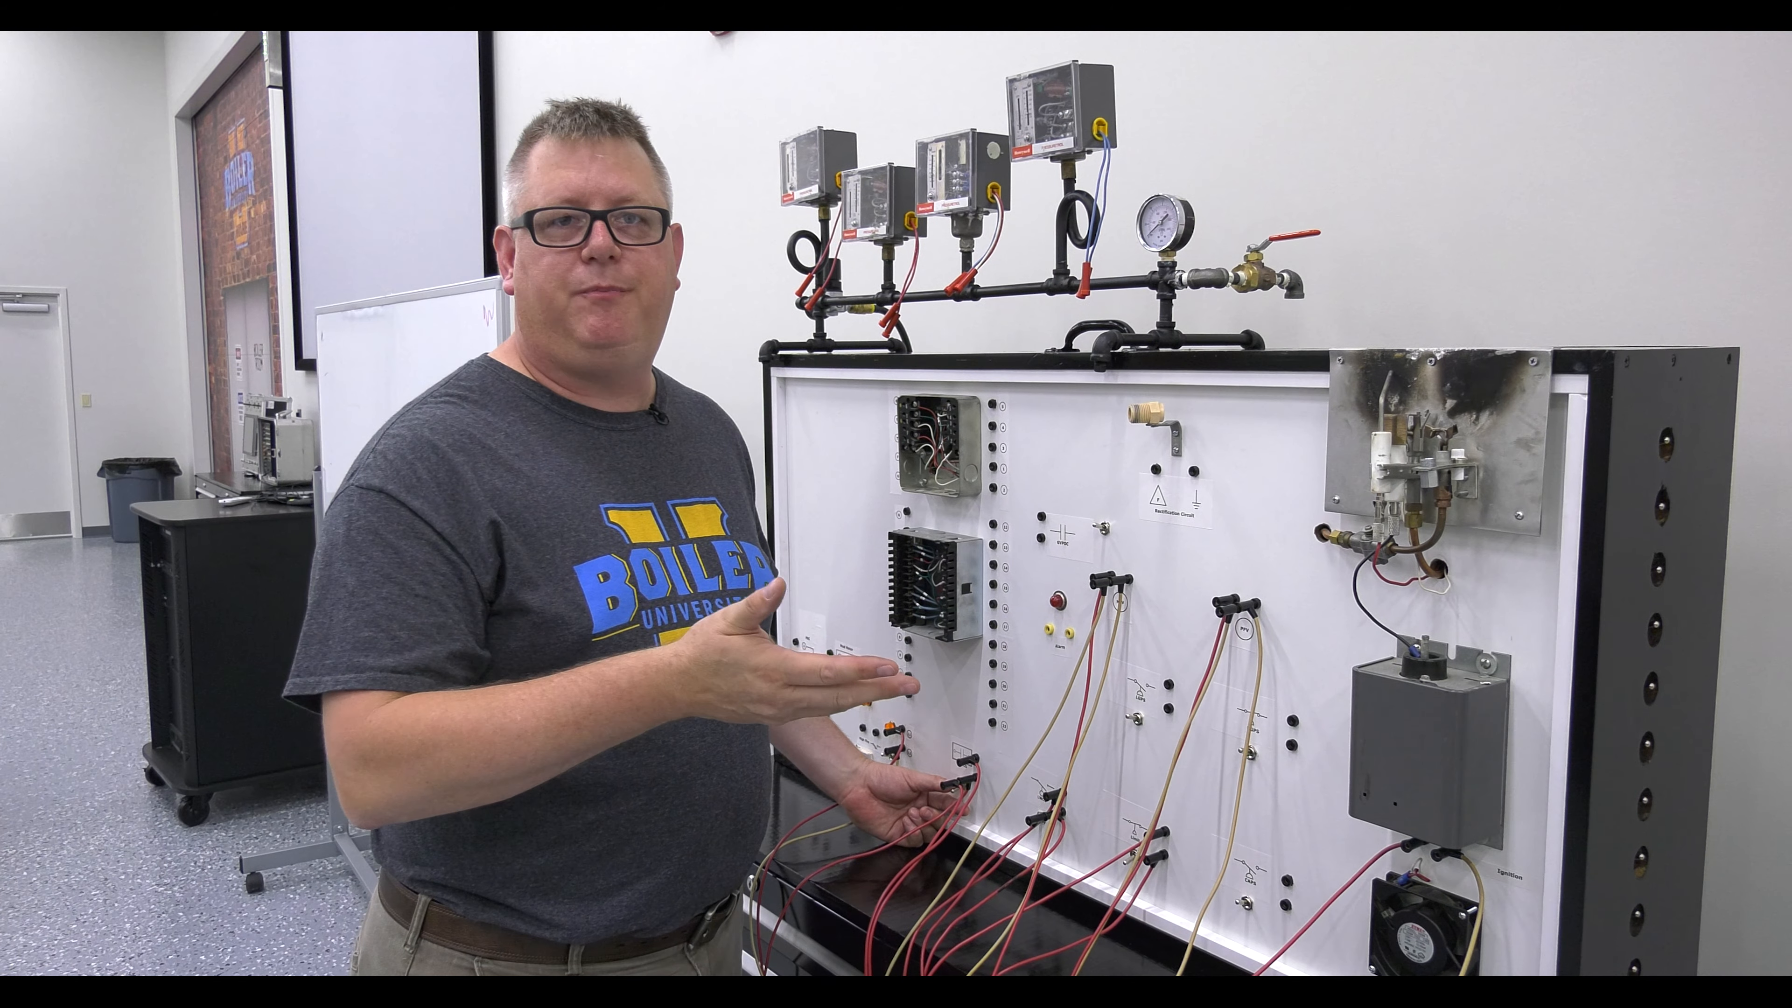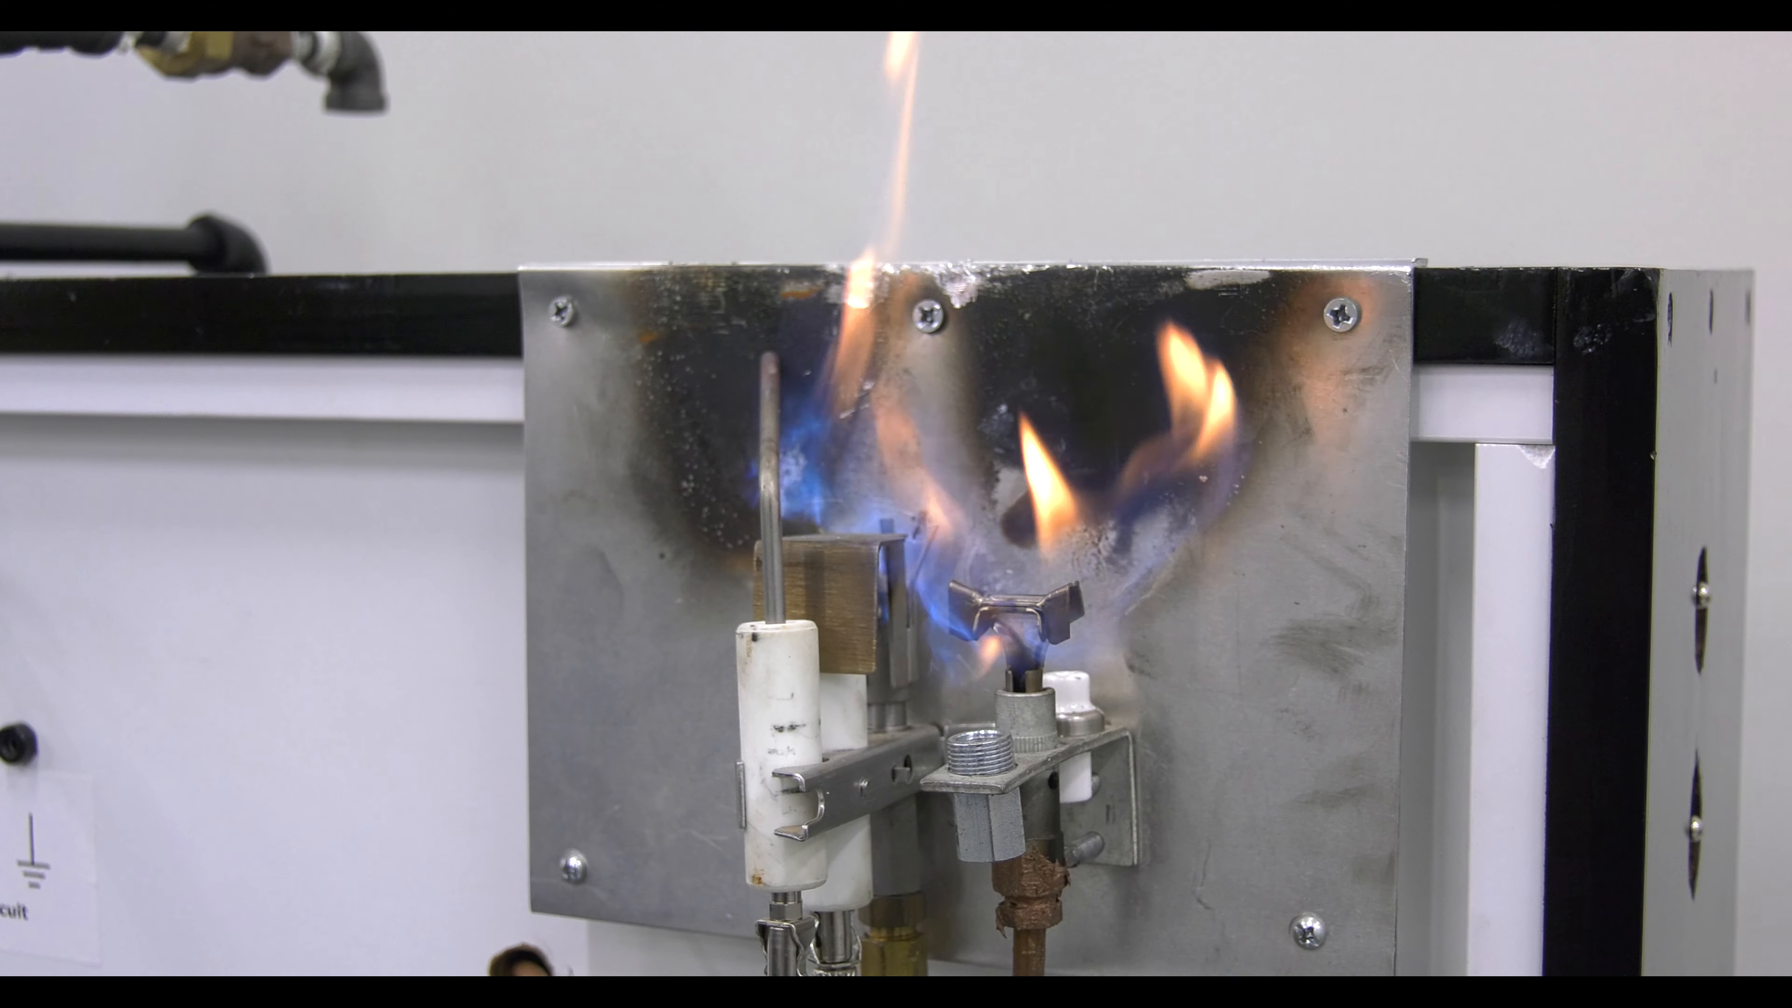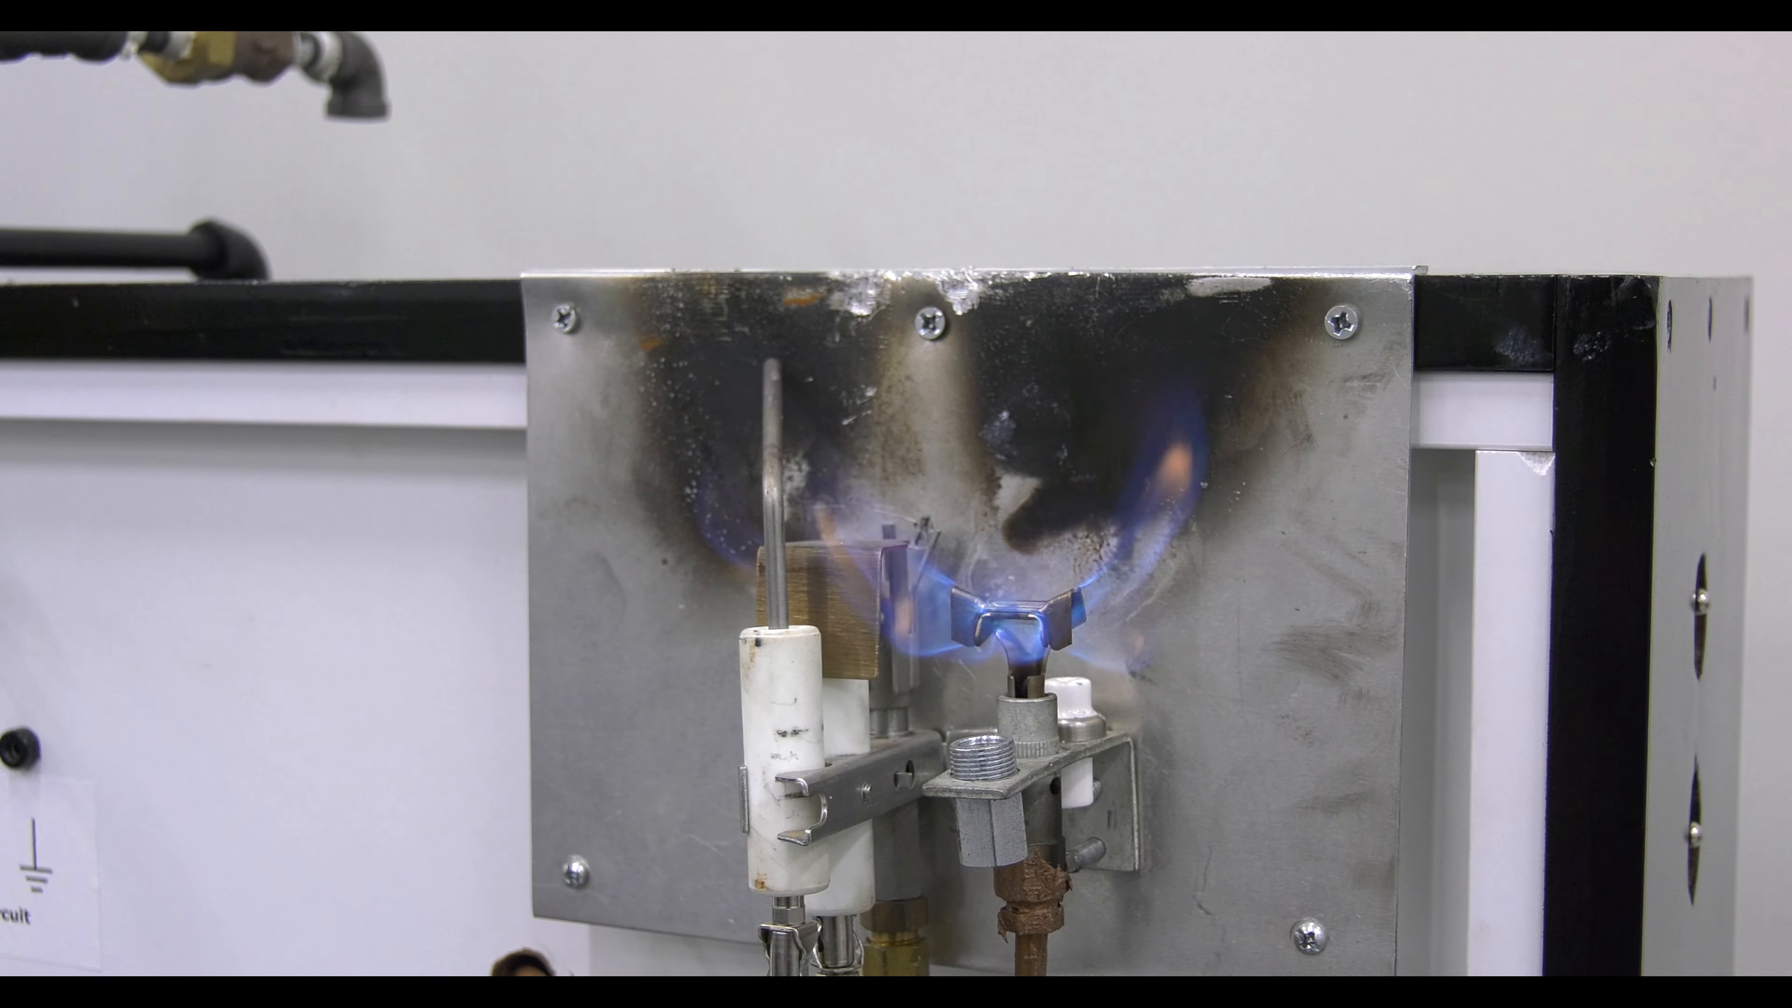The second type of pilot is an interrupted pilot. On our light off sequence we'll get spark, we'll get pilot, then we'll get main, and then once that's proven our spark and pilot will extinguish. So we're proving the main flame on its own. That's an interrupted pilot.